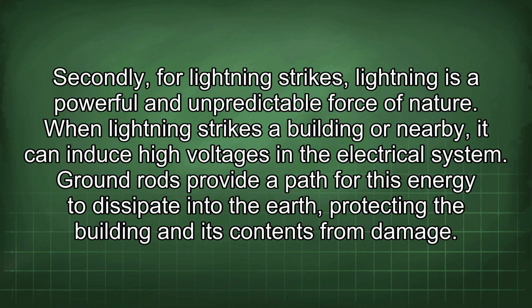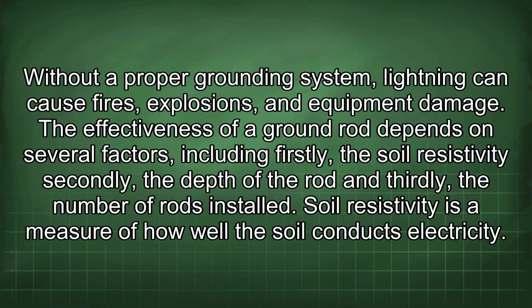Secondly, for lightning strikes, lightning is a powerful and unpredictable force of nature. When lightning strikes a building or nearby, it can induce high voltages in the electrical system. Ground rods provide a path for this energy to dissipate into the earth, protecting the building and its contents from damage. Without a proper grounding system, lightning can cause fires, explosions, and equipment damage.